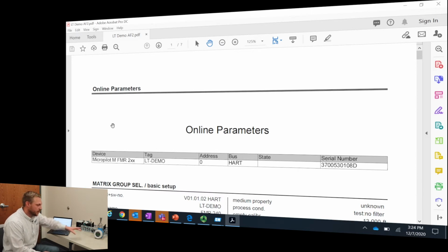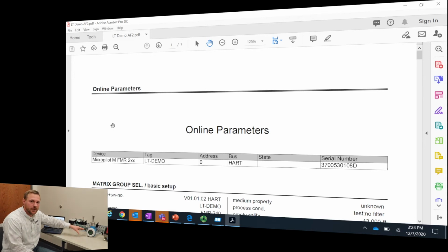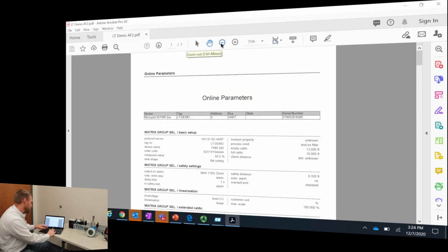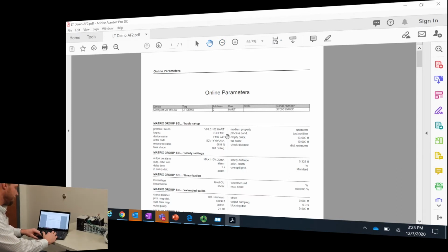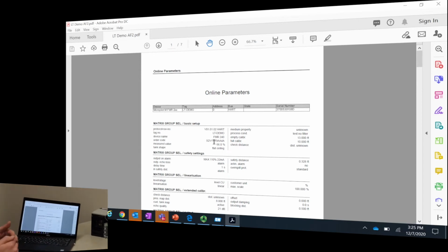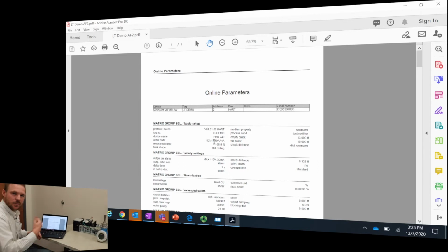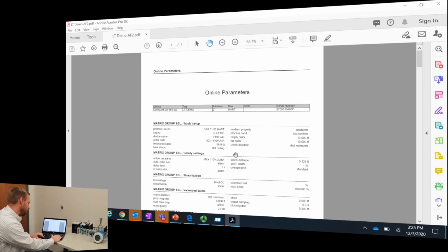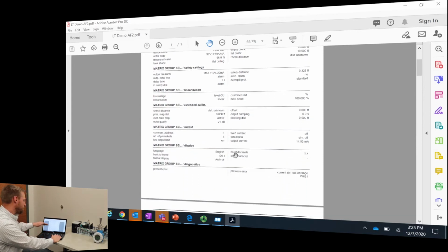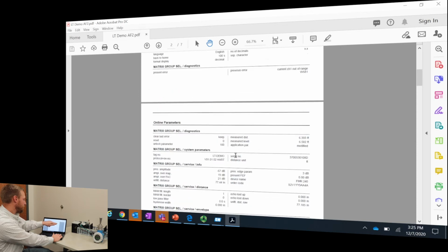All of the parameters necessary for resetting up this device or for replacing it with a different device are all documented in this sheet. This sheet tells us everything we need to know about the device, including model number, serial number, tag number, order code for replacing it. The order code details what the process connection is, what the output is, what the hazardous area rating is, all sorts of information. As we scroll down, we can see the amount of mapping inside of it, the 4 to 20 milliamp scaling. It prints out the last previous error that it had. In this case, it had an error of W681 indicating current out of range. We can use that for troubleshooting the device when we connect into that device. If we know it had an issue in the past, that's a clue as to what the issue was that it was encountering.